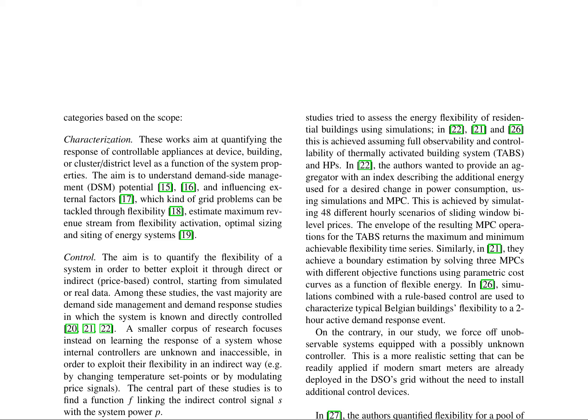The control logic of heating systems is governed by thermal models crucial for efficient operation. In the heat pump control logic, two temperature sensors in the water tank and one inside the house determine the working mode based on a moving average of external temperature. When heating is required, the system employs a hysteresis on the internal temperature, activating the circulation pump when temperature falls below a predetermined threshold. In cooling mode, the control logic modulates water temperature through a three-way valve. The heat distribution system is modeled from first principles, focusing on floor heating, with an analytical expression derived for the temperature profile along the pipe.